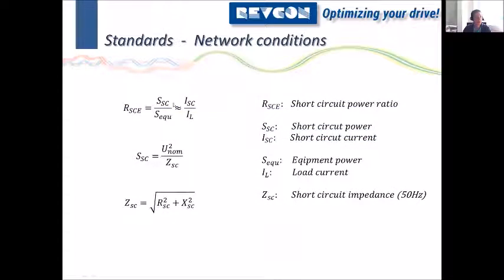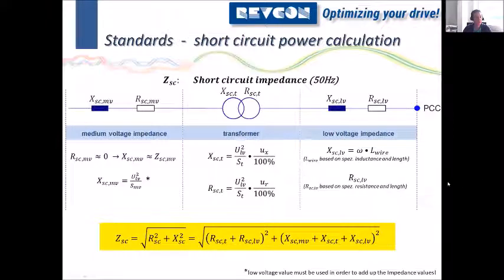So first of all, to calculate this, we can use the calculation from the IEC, which is short circuit power divided by equipment power. This is roughly the same as short circuit current divided by load current. It's not exactly the same, but as a quick estimation, it can definitely be used.